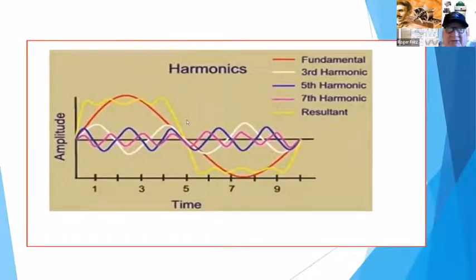It's the same way a radio was built. So what happens is you have your fundamental voltage out here, and then you have what they call third harmonics, which are 3 times 60, or 5 times 60. These showed up, or 7 times 60. And these were the ripple currents that were actually seen also going into the drive with an oscilloscope. And then you had a true resultant of current. So the current waveform on the input looked very non-sinusoidal. They call it nonlinear power. And from that nonlinear power, you create a lot of issues.